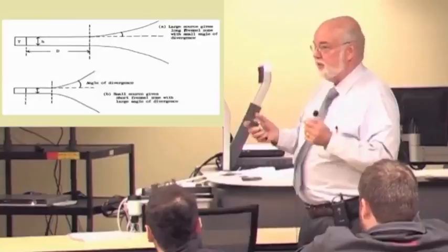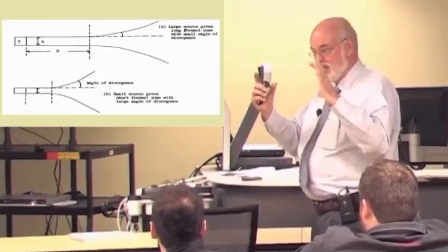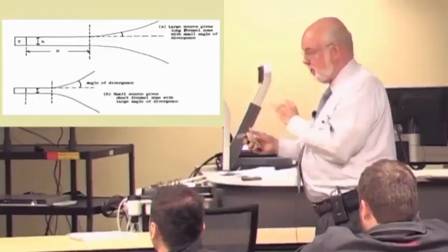So if you fire 10 of them or 20 of them at the same time, you've effectively created a single bigger transducer. Then you just shift down one or two and fire that next group and repeat that to get your moving image. And I think that's all the time we'll spend with that.